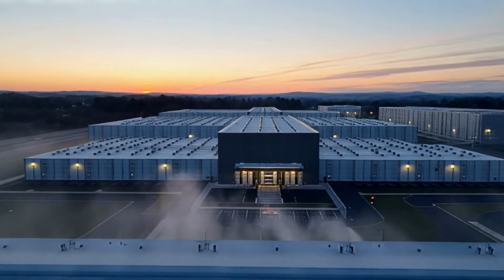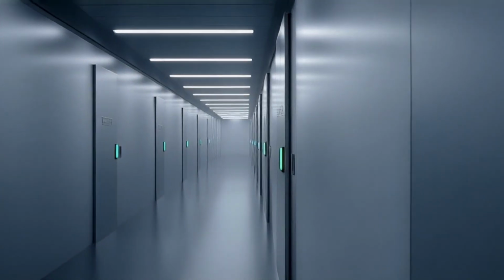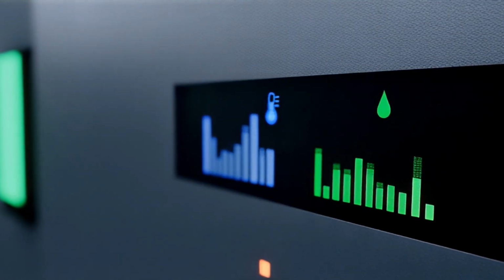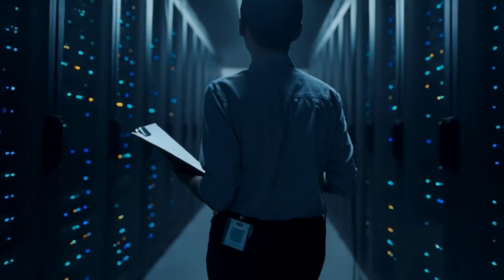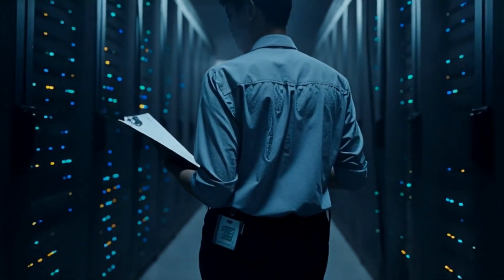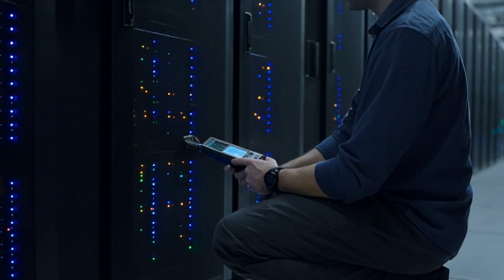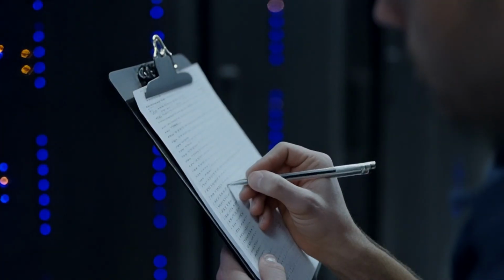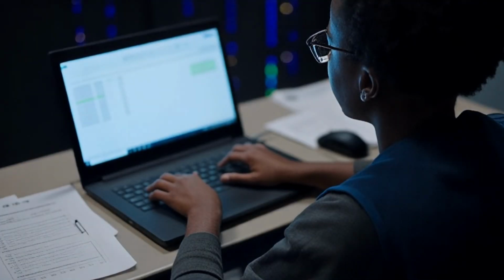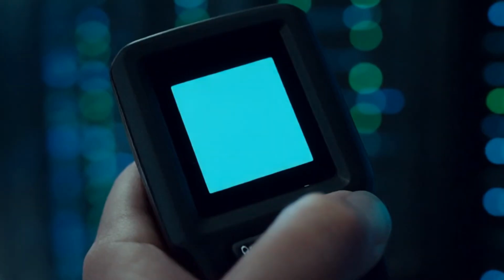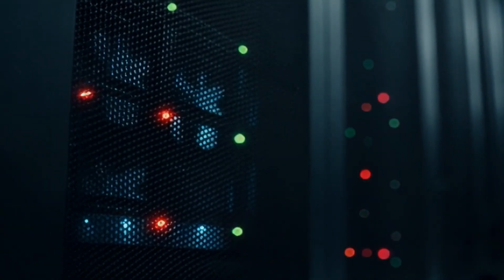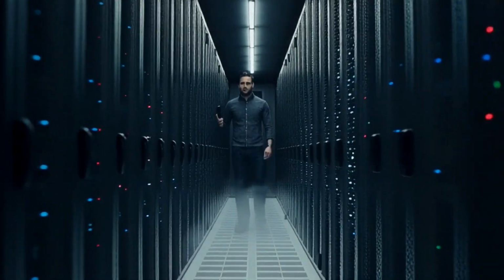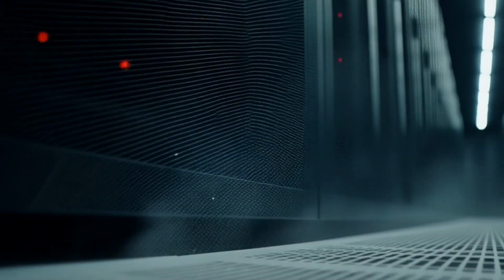This facility had multiple server rooms spread across a large site. They needed continuous environmental visibility, temperature, humidity, and dew point, and they needed reliable access control at each room entrance. Up to this point, everything was done manually. Technicians performed regular patrols, reading data and logging it by hand. But by the time someone noticed a hot aisle running too warm, they were already reacting instead of preventing. And when access logs needed to be reviewed, the data was fragmented and inconsistent.